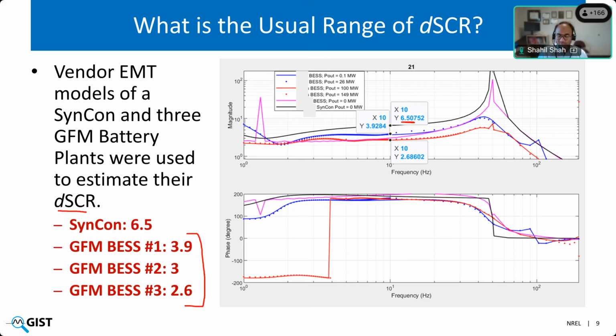The second reason is most of the instabilities we see coming from the big grid fall within this 1 to 30 hertz range, 1 to 25 or 30 hertz range. And these performance metrics are really targeting those big grid instabilities. And that is the second reason why we want this behavior of voltage source behind reactor, to mitigate those big grid stability issues.